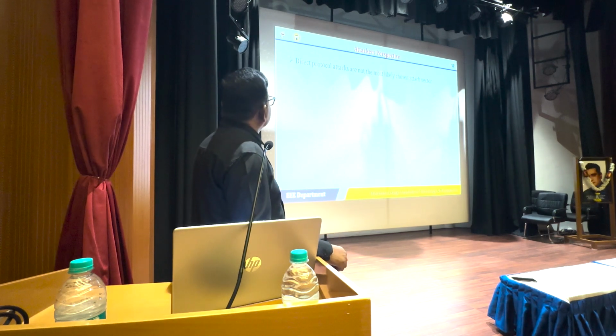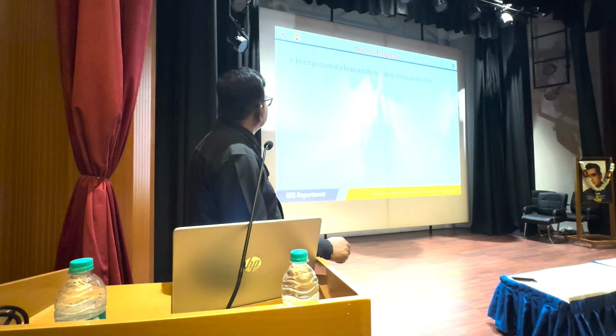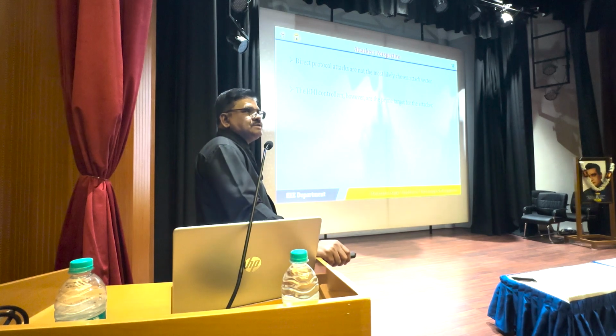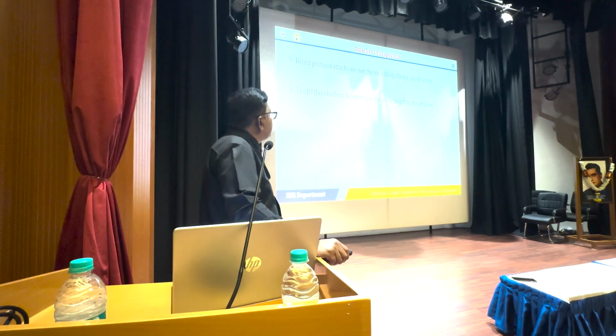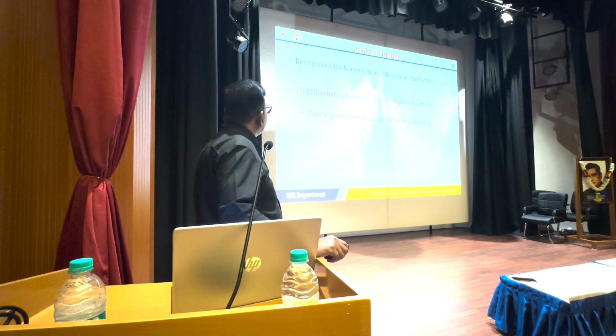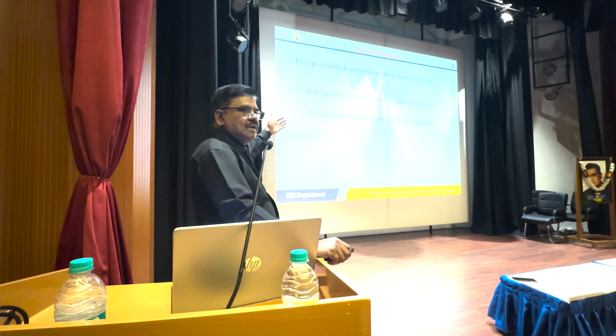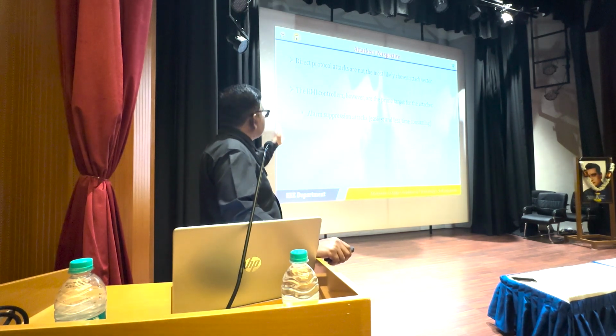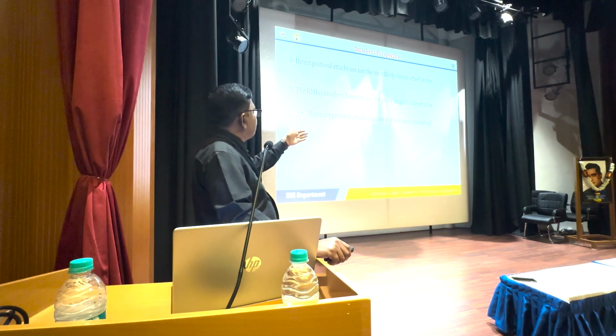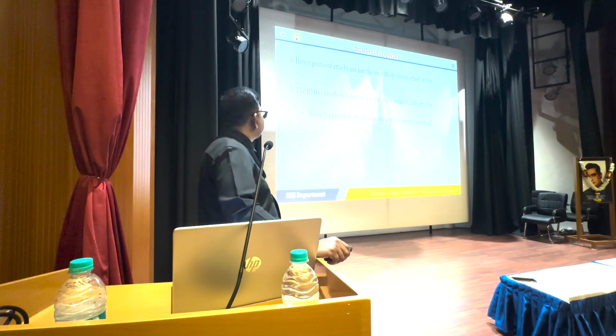Then what is the attacker's perspective? Direct protocol attacks are not the most likely chosen attack vector. They will not choose the direct protocols. However, they will target HMIs, the human machine interface controllers. That is the prime target of the attackers. By attacking the HMI, they will suppress the alarm. That is the easiest and least time consuming attack.